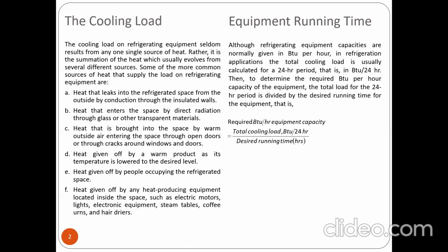Now, equipment running time. Although refrigerating equipment capacities are normally given in BTU per hour, di ba yung capacity, in refrigeration application, the total cooling load is usually calculated for 24 hours, hindi 365 days. So, that is in BTU per 24 hours talaga yon. So then, to determine the required BTU per hour capacity of the equipment, the total load for the 24-hour period is divided by the desired running time for the equipment. So required BTU per hour equipment capacity is the total cooling load, BTU per 24 hours, divided by the desired running time.